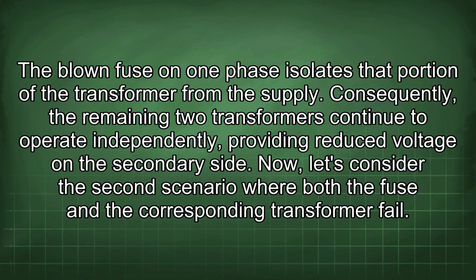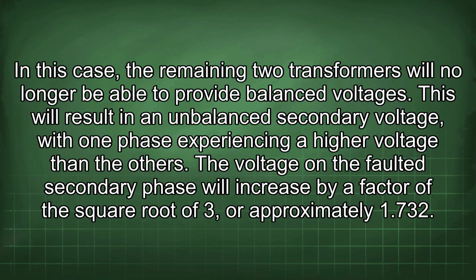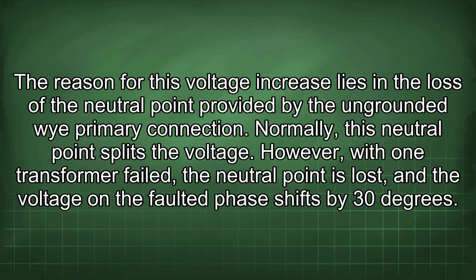Now, let's consider the second scenario where both the fuse and the corresponding transformer fail. In this case, the remaining two transformers will no longer be able to provide balanced voltages. This will result in an unbalanced secondary voltage, with one phase experiencing a higher voltage than the others. The voltage on the faulted secondary phase will increase by a factor of the square root of 3, or approximately 1.732.